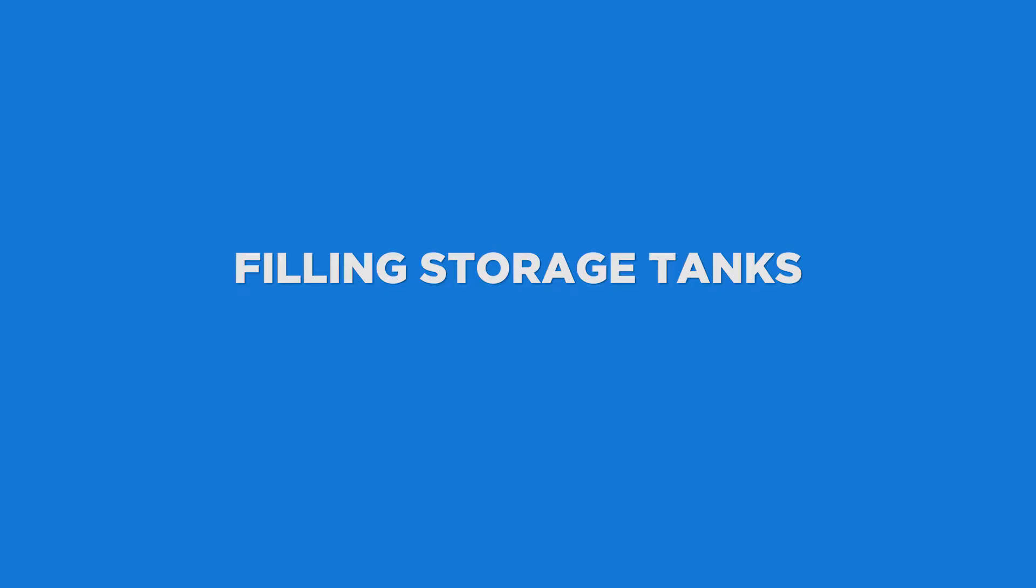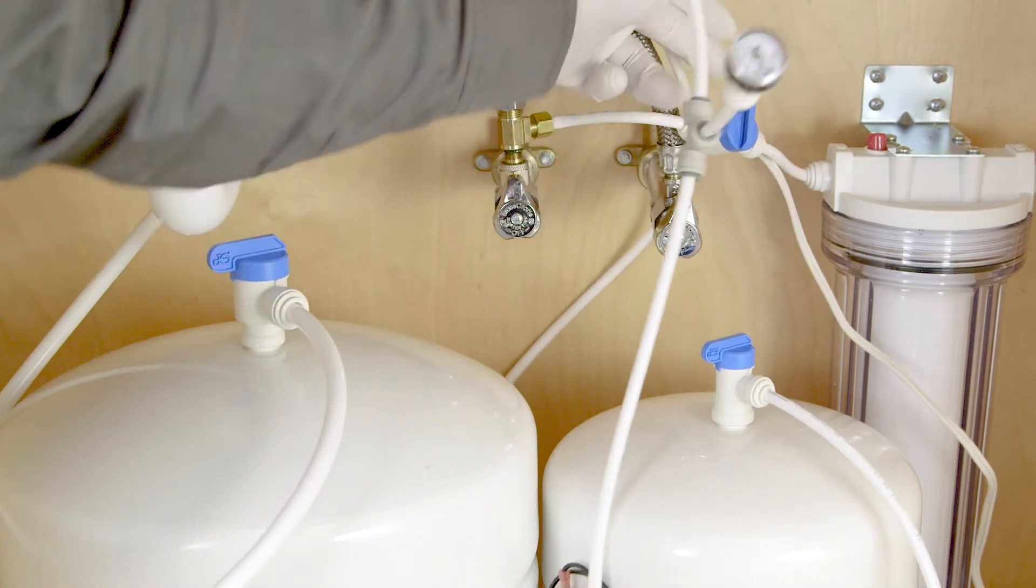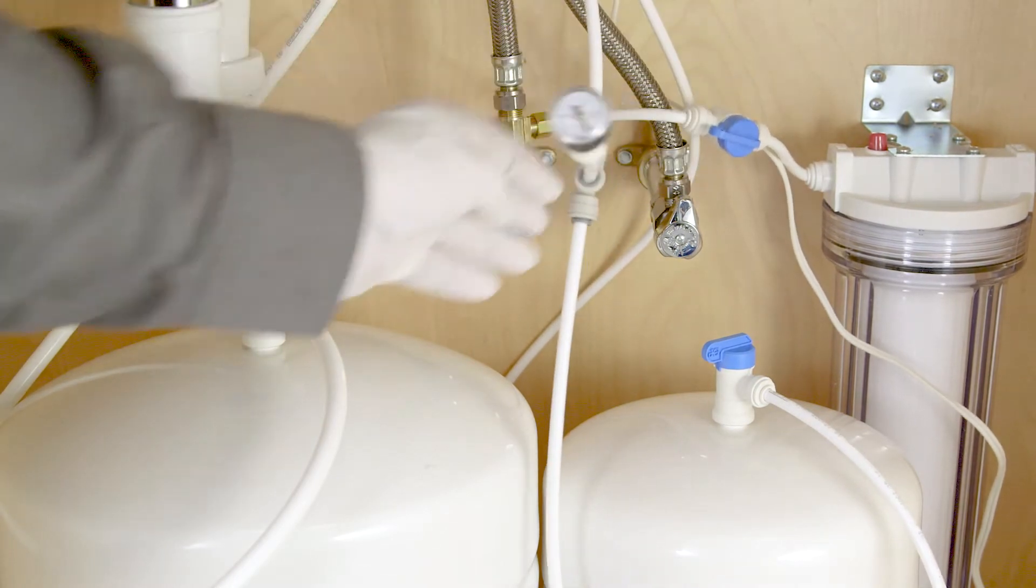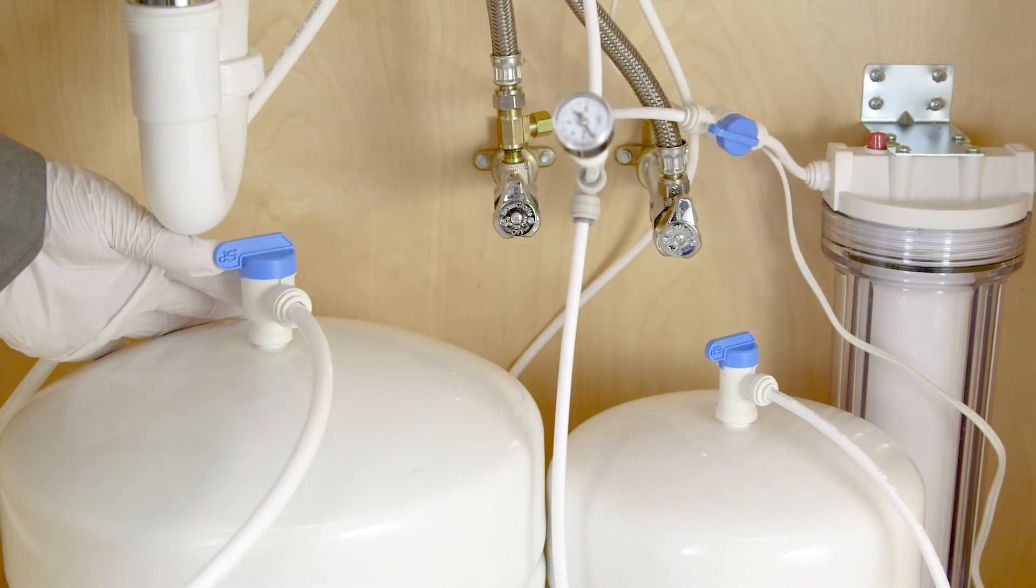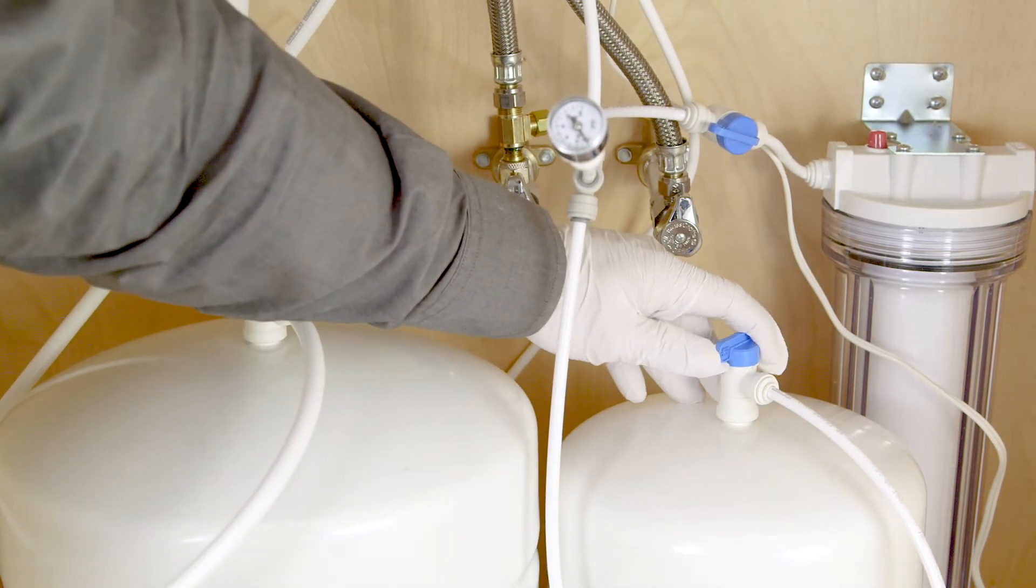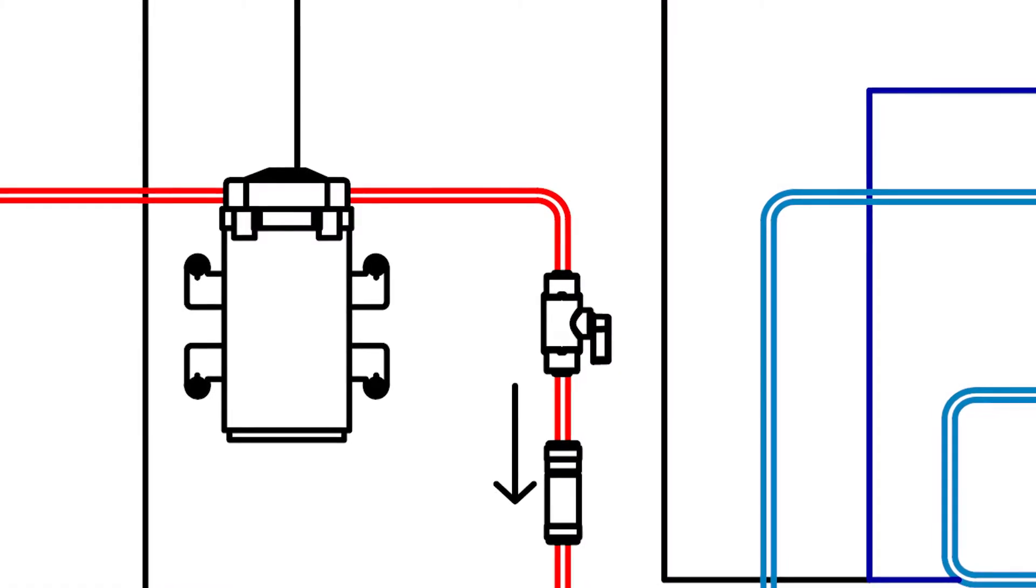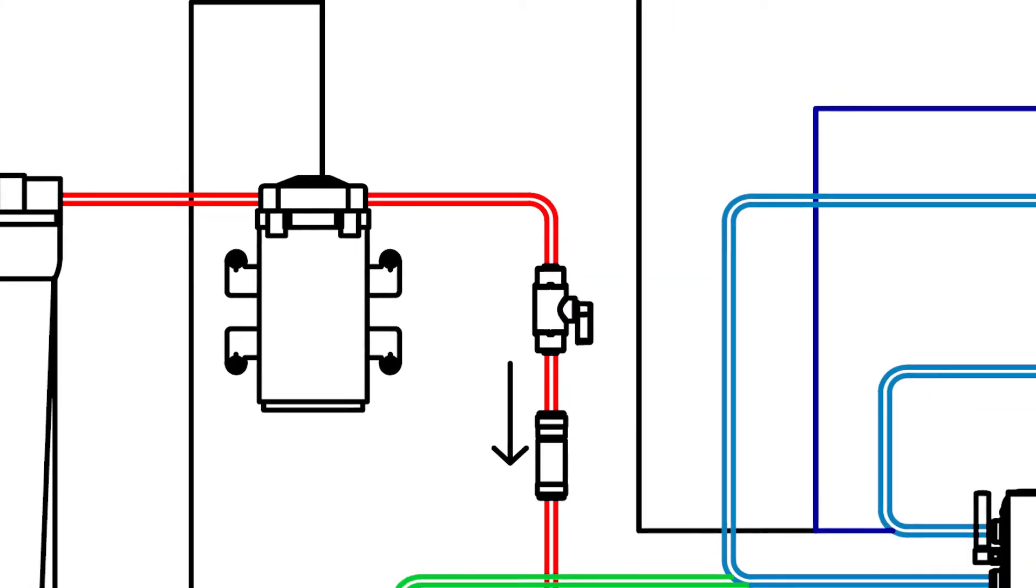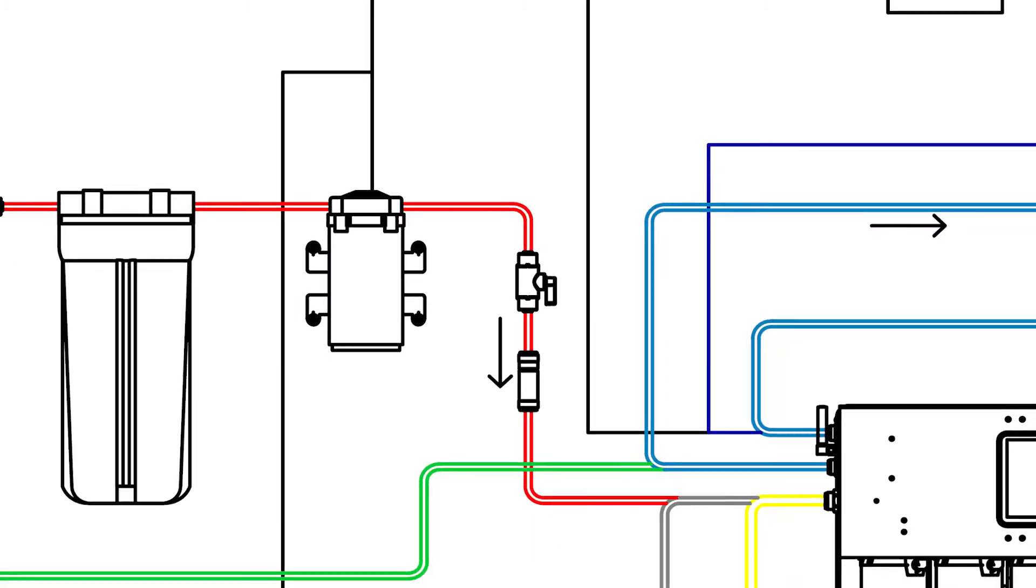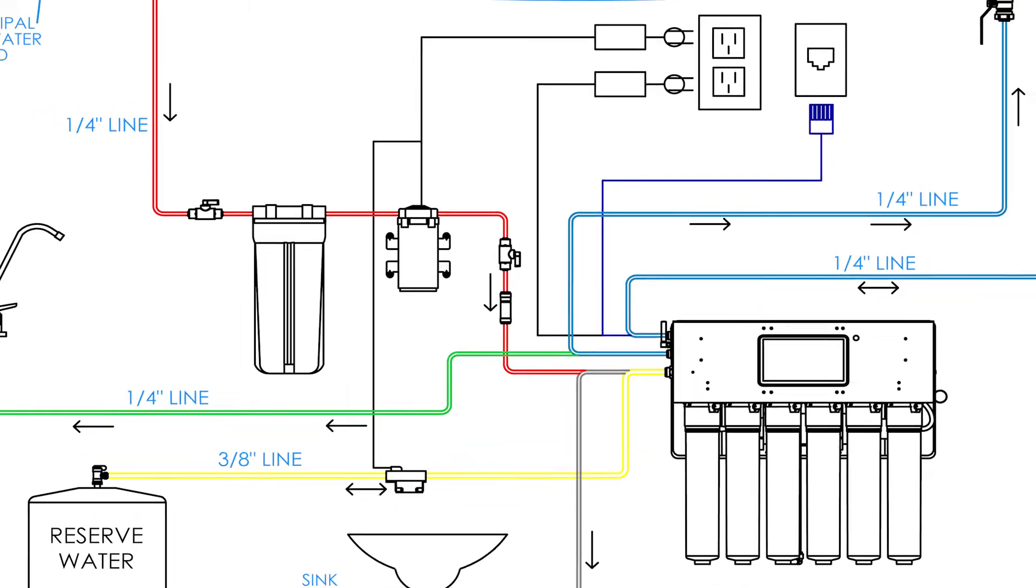Filling the storage tanks. Now you can open the source water valve at your municipal supply. If you have a pre-filter, check that any shutoff valves in front of or behind the filter housing are in the open position. To open the RO reserve and dental water tanks, turn the tank ball valve knob in line with the tubing. You can visually confirm water is flowing freely to the booster pump at this point. Once you have water flowing to the booster pump, you can plug it in and verify it's working. The RO and dental tanks will slowly begin to fill.